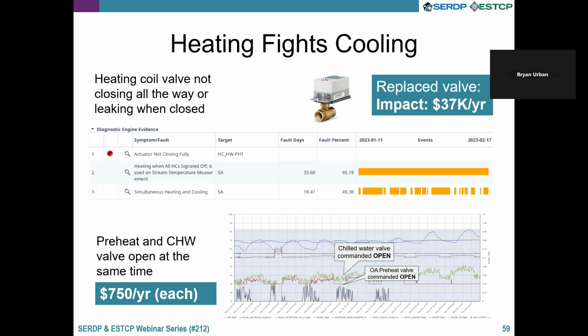Another one is when heating systems fight with cooling systems. So here you might have a zone that feels comfortable, but it's heating and cooling at the same time. On the top, there's an example where a heating coil valve was not closing all the way, or leaking fluid or passing fluid when it was closed. As a result, you have to heat and cool at the same time to maintain temperature in the zone. Again, nobody would report a fault, but if you can see that happening from the control system, you could potentially resolve tons of energy waste.